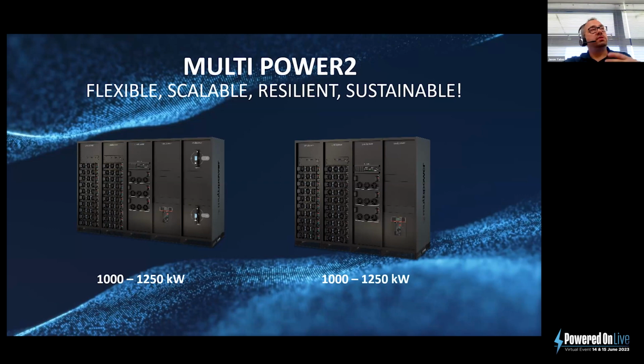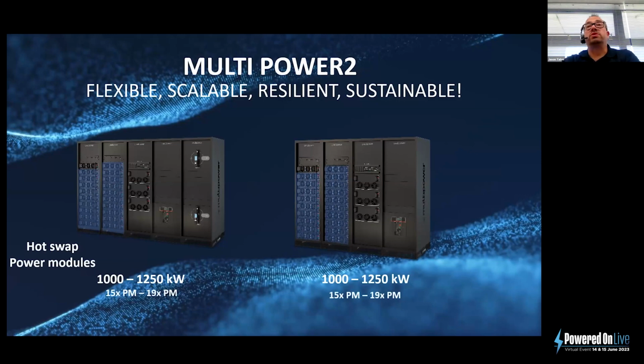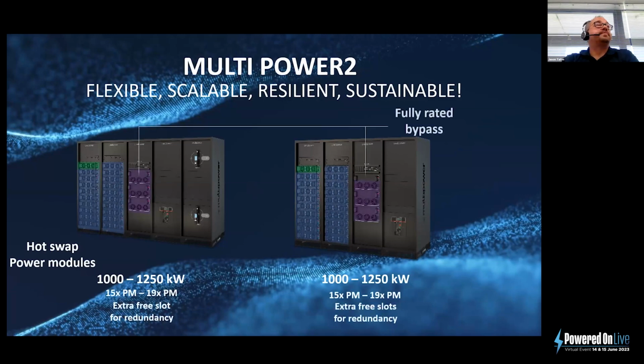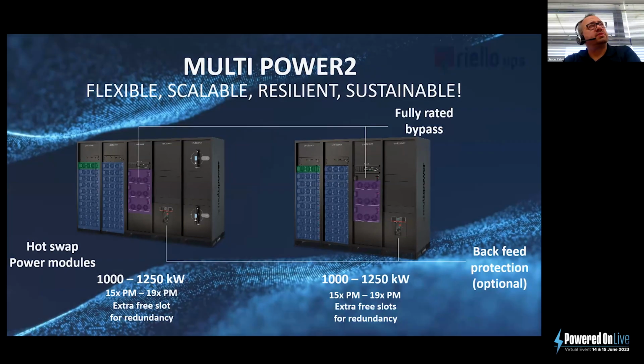So the whole point of this system is it's flexible in terms of its modules. It's scalable in terms of it can be increased and decreased in size accordingly, automatically if you wish to. It's resilient because obviously you've got the redundancy, and it's sustainable because of the technology, which I'll come on to in a second. So again, fully hot swappable modules, fully rated bypass switch, and redundant slots. But in this case, this has a backfeed protection as an option. So again, it's flexible for all kinds of installations.